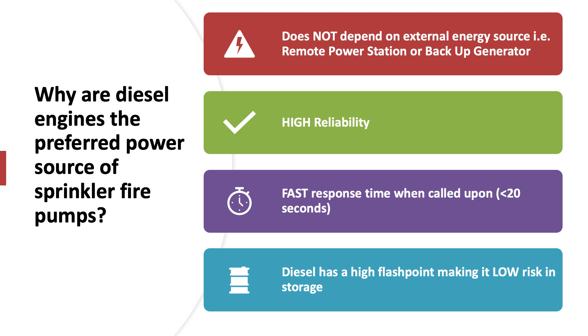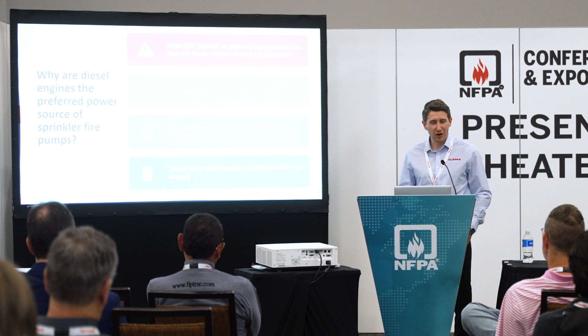As I said, high reliability, very fast to respond. Our engines are designed to come online within 20 seconds and be supporting the fire pump at any flow condition. And finally, diesel fuel itself has a high flash point, which means in storage it's a relatively low risk fuel compared to gasoline and other fuels.